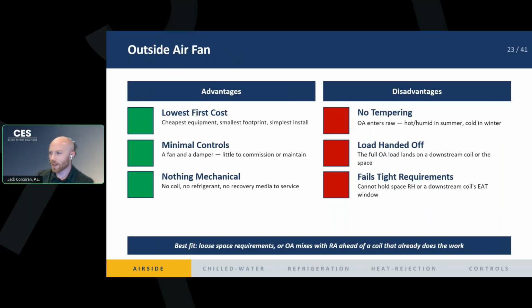So what about outside air fans, right? We've talked a little bit about the advantages and disadvantages, but here they are laid out for us. So it's super cheap, right? You don't have any mechanical cooling. There's no expensive compressors or components. It's just a fan and a louver that brings your outside air in. You don't have any controls. There's no temperature changing. It's just bring in the outside air at the amount of CFM you need. And there's no complicated coil, no refrigerant, no wheel or plate recovery media that you need to service every once in a while. A disadvantage, right?